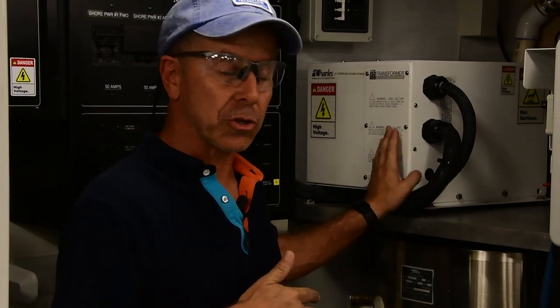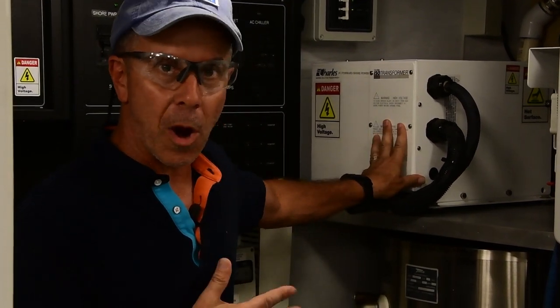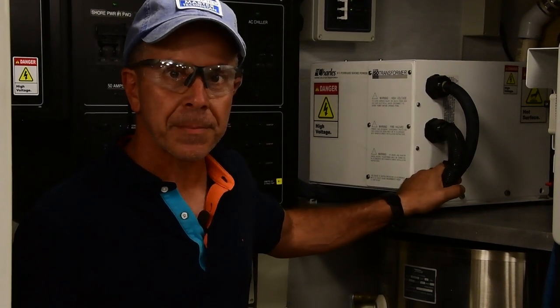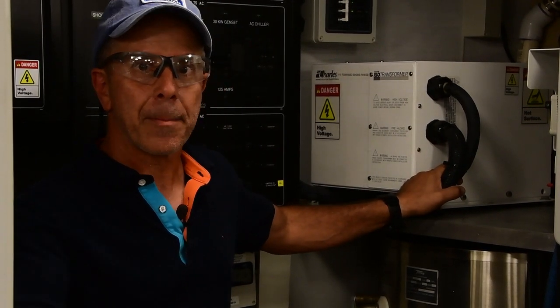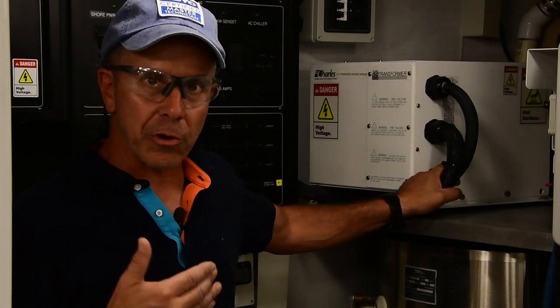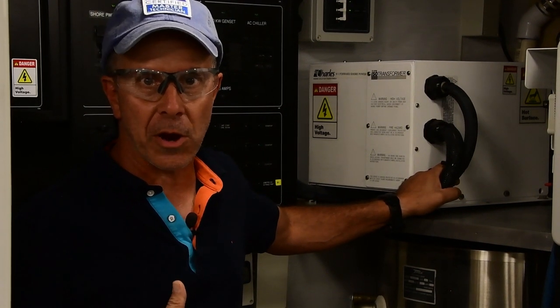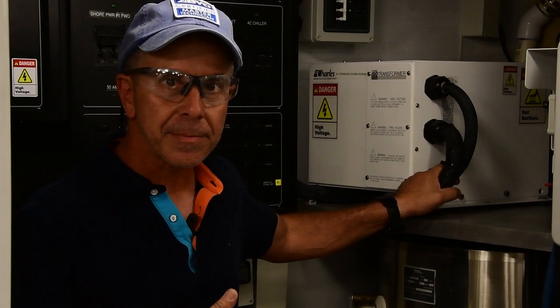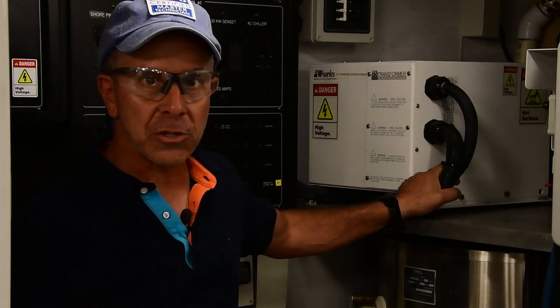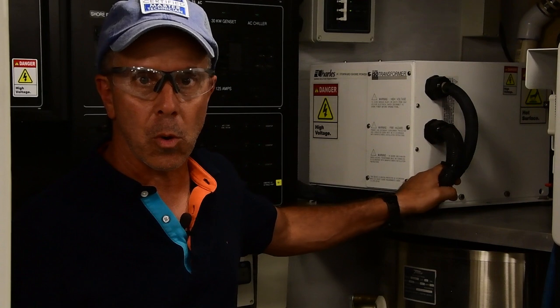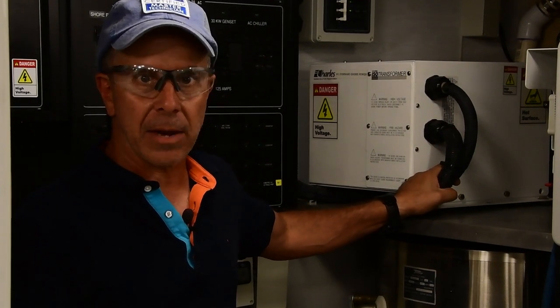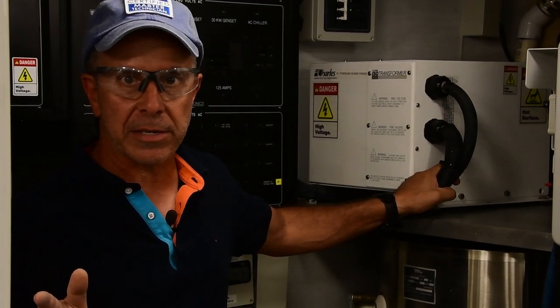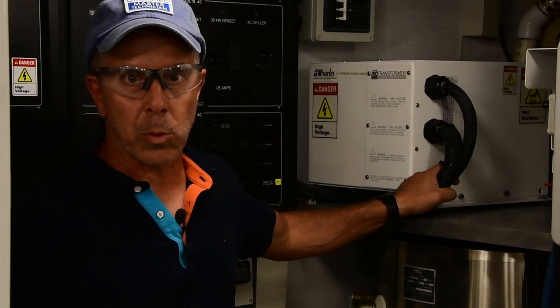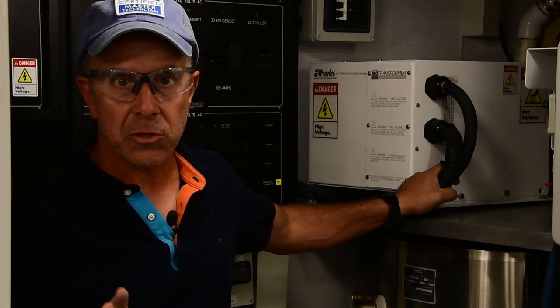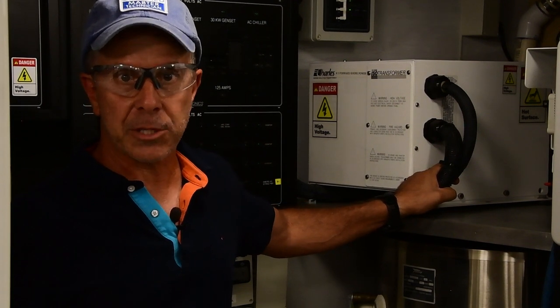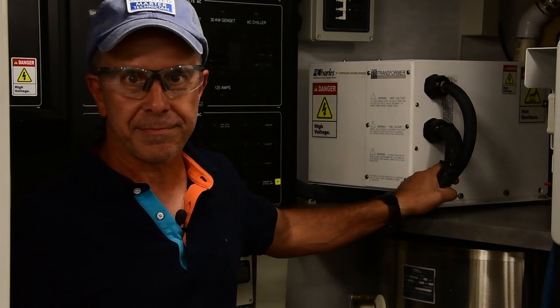Larger transformers like this one happens to be wired as an isolation transformer. Larger transformers like this typically have a 240 volt inlet, what we call a primary power that's being supplied to it, and then a 120 volt and 240 volt outlet for secondary. Again, whatever power is coming in, if it's incorrect in any way, typically the transformer will either correct it or it won't work at all, so they get no power on the boat, but that's better than having the wrong power on the boat.